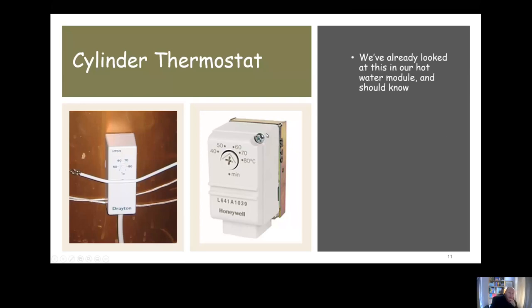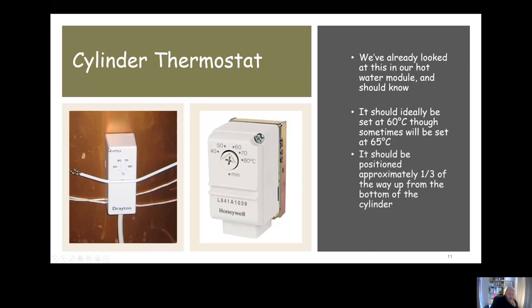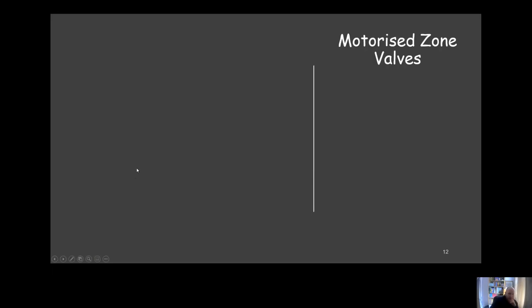Cylinder stats, we should already know a lot about this. We've talked about it in hot water. Should be set at 60, minimum is 60, maximum is 65. Should be in direct contact with the cylinder. Positioned a third of the way up from the base of the cylinder, etc, etc.